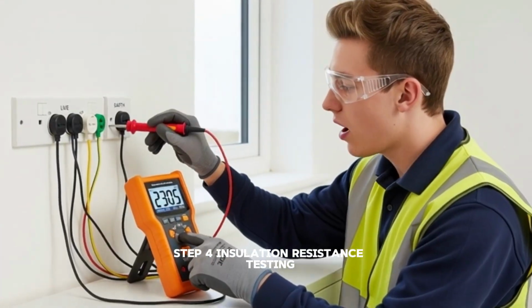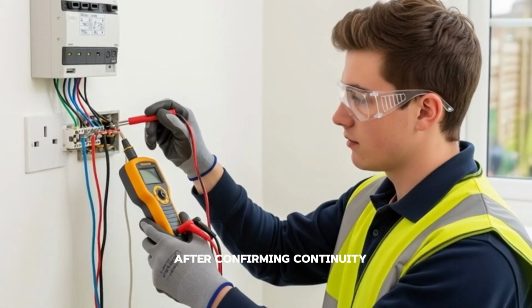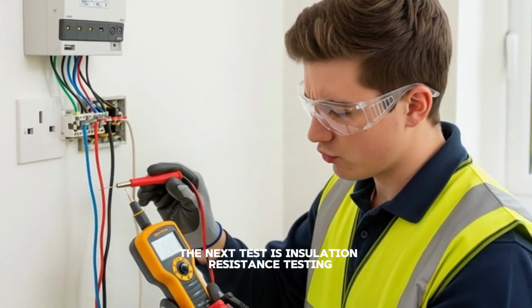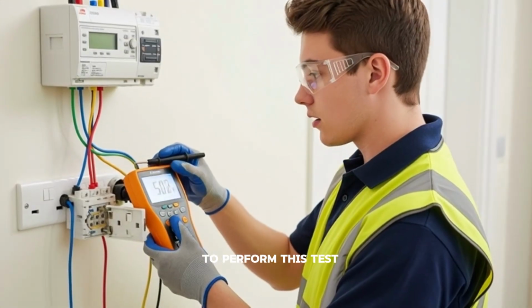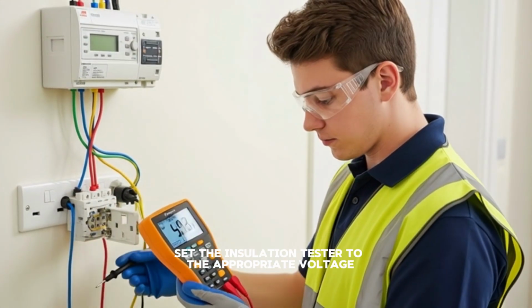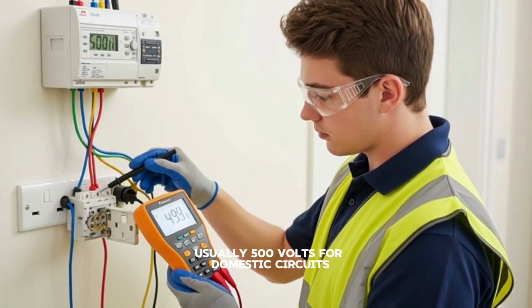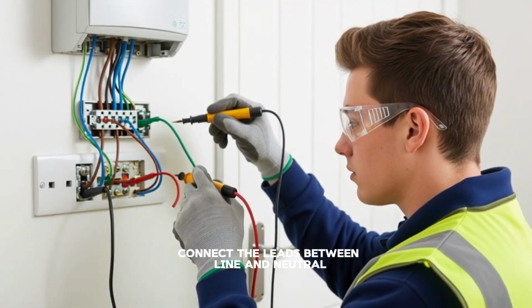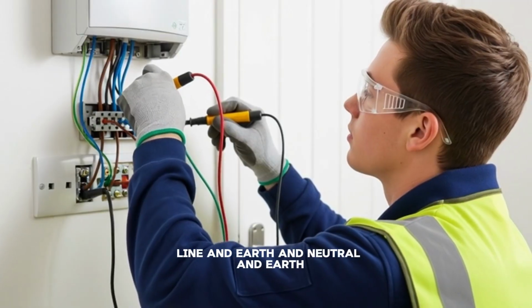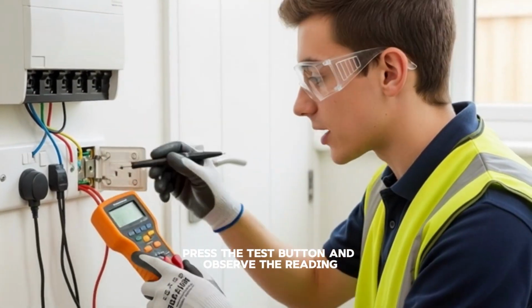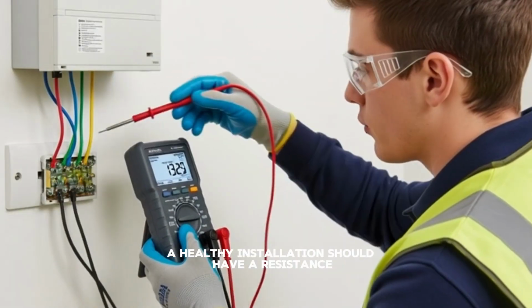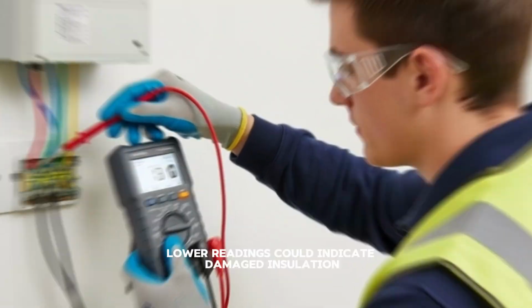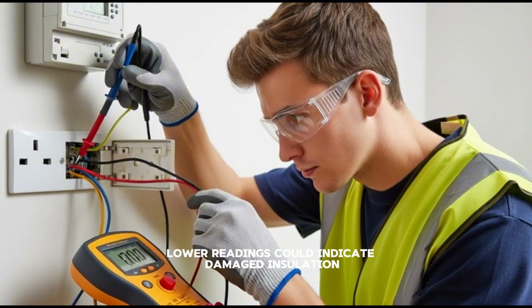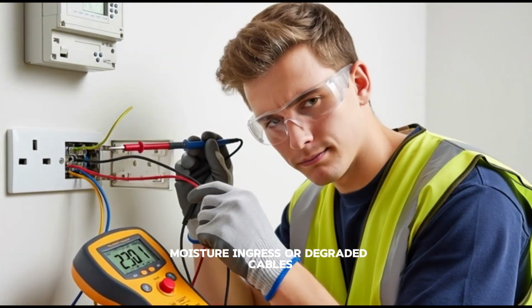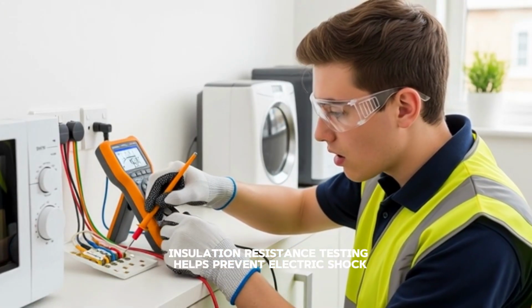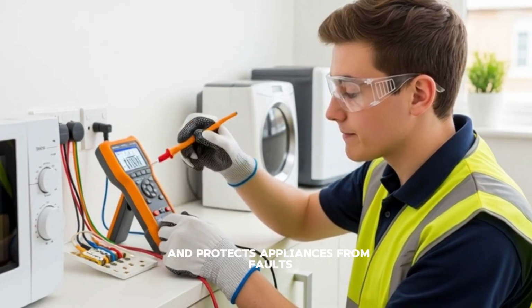Step 4. Insulation resistance testing. After confirming continuity, the next test is insulation resistance testing. To perform this test, set the insulation tester to the appropriate voltage, usually 500 volts for domestic circuits. Connect the leads between line and neutral, line and earth, and neutral and earth. Press the test button and observe the reading. A healthy installation should have a resistance reading of at least 1 megaohm. Lower readings could indicate damaged insulation, moisture ingress, or degraded cables. Insulation resistance testing helps prevent electric shock and protects appliances from faults.